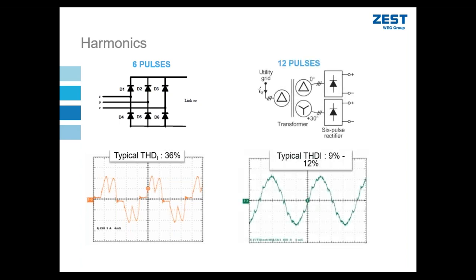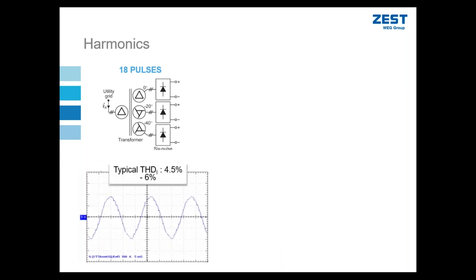If I look at a 12 pulse bridge rectifier with phase shift transformer, my actual measured waveform is shown below. This is for a series connected 12 pulse rectifier. Typical THDI in this case is between 9 and 12% at full load. Then I go to the 18 pulse scenario. I have a typical THDI of 4.5 to 6%. My current waveform is starting to look very smooth, very sinusoidal.